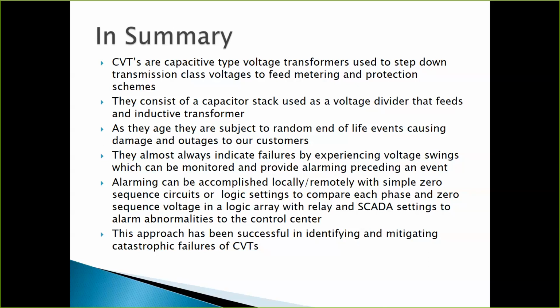As you get above 44 kV, 100 kV and above, it doesn't become cost effective to use an inductive type. They're so huge, they're cost prohibitive. So the majority of utilities at 100 kV and above will use some type of CVT. So the demarcation is basically based upon your voltage class. But yes, absolutely we use them for metering applications, potential applications for over/under voltage schemes. But basically they're at 44 kV and below for more of a distribution class stuff. And thank you for your question.